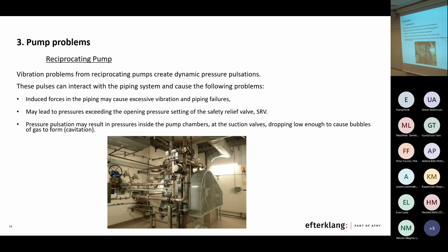When you have reciprocating pumps, this is also just one single example. There are a lot of problems with reciprocating pumps. But I want to highlight, anyway, the dynamic pressure pulsations from this. These pulses interact with the connecting pipe systems and can induce forces on the pipe system itself. But they can also lead to the safety relief valves being opened by mistake, so to speak. And the valves can also be worn and broken.